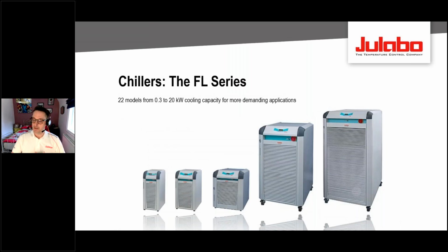But if you're in a bigger laboratory, one thing you can do with chillers is attach different devices. So instead of having one chiller on every Rotavap, maybe you'll have a medium-sized chiller that feeds 4 or 5 Rotavaps. Then you need to start thinking about pump capacity. So the main difference between families of chillers isn't just temperature or power, it's also the pump.